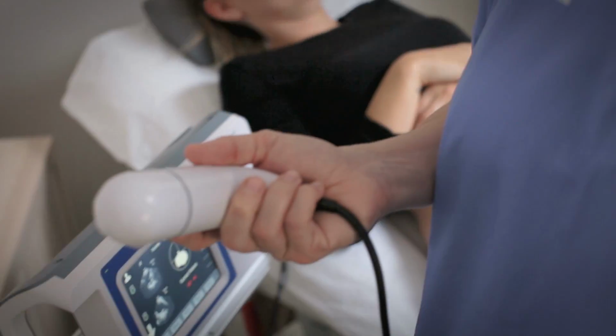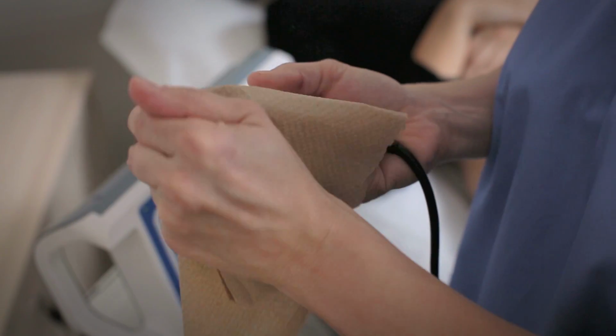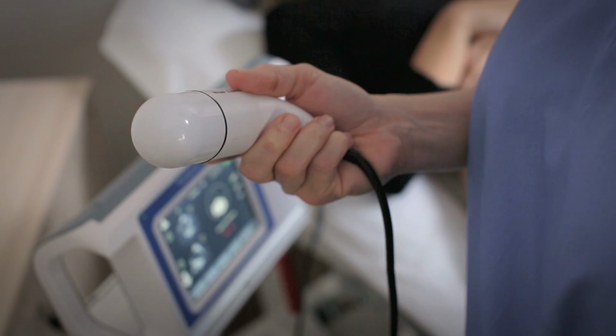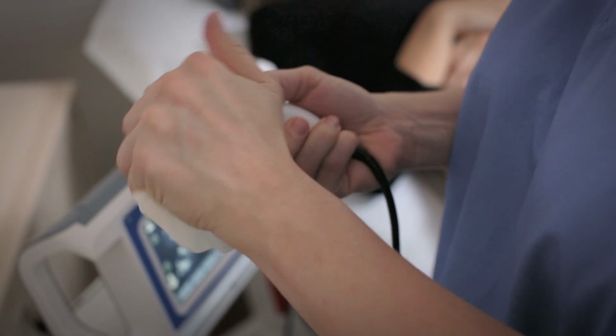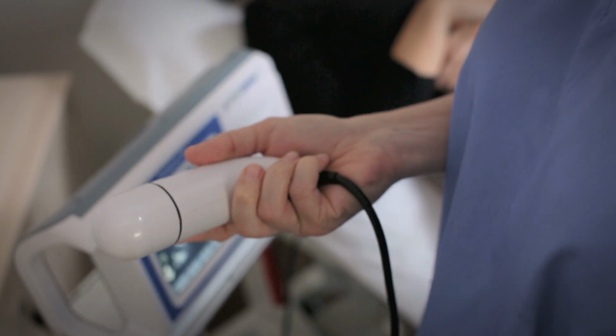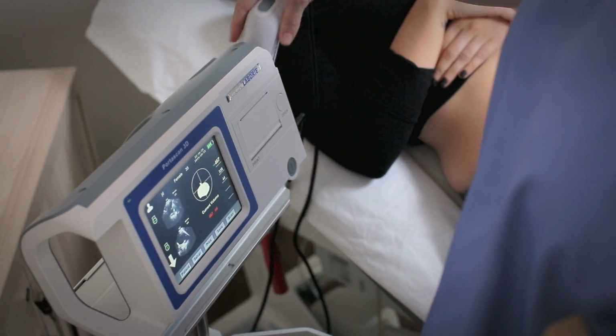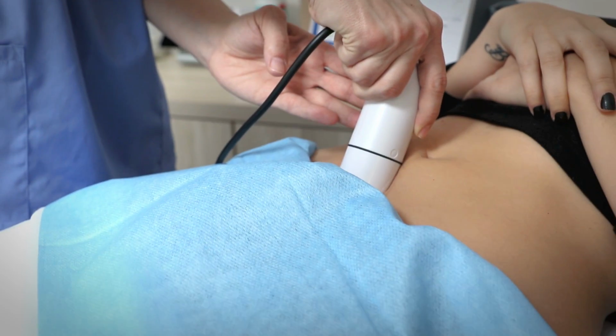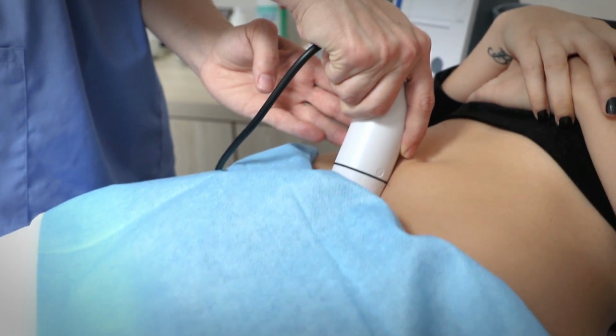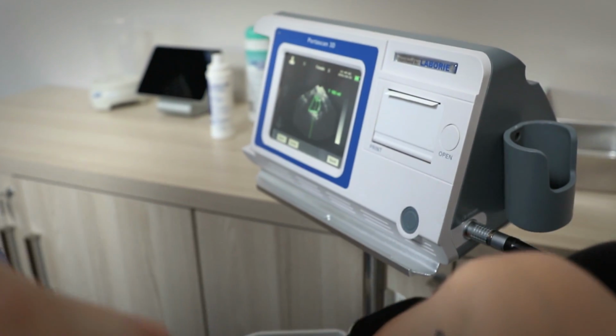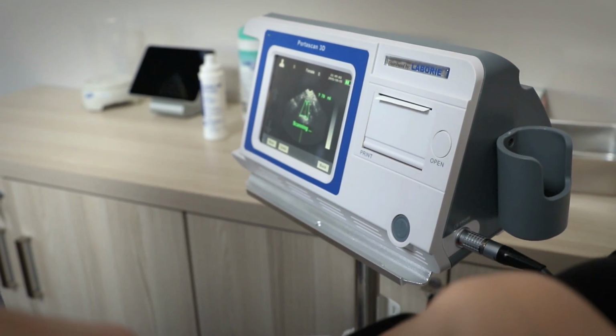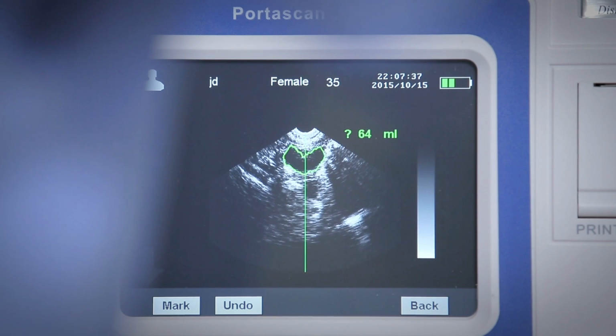If the patient has a large abdomen or pannus, move it up and out of the way and scan lower on the abdomen. Do not scan directly over scars. This may obstruct the scan. It is critical to hold the probe still during the scanning phase, as 12 separate images of the bladder are taken during one scan to calculate an accurate volume.